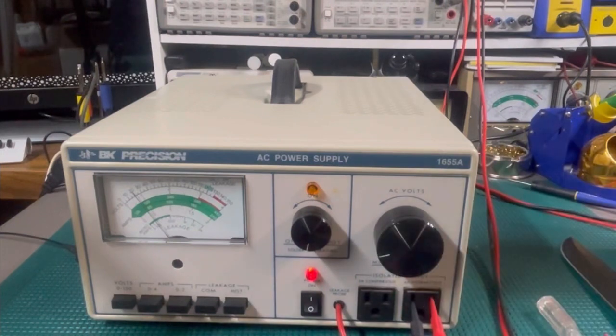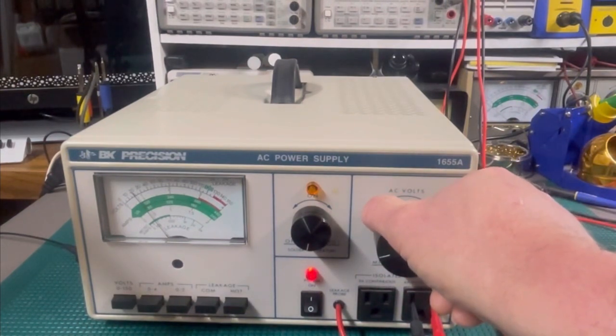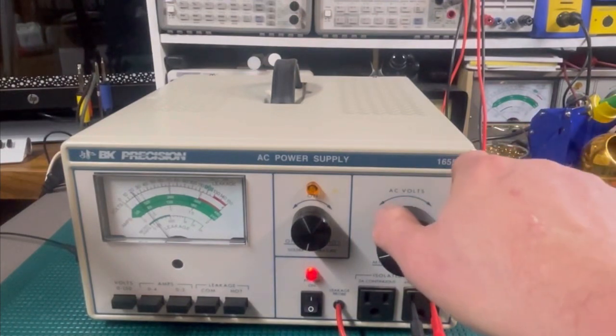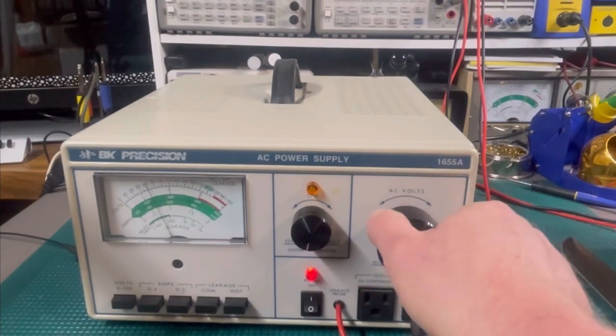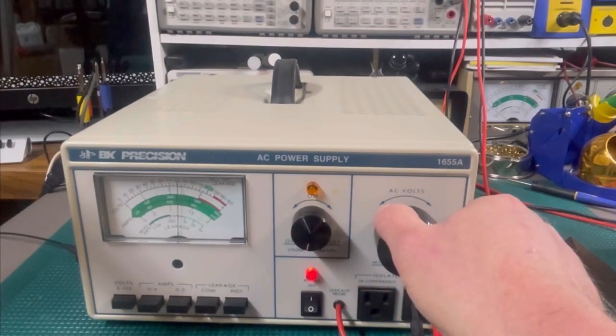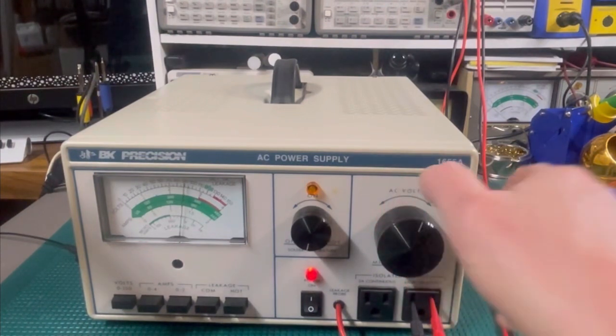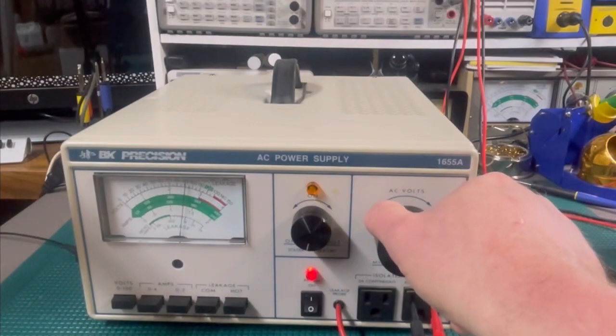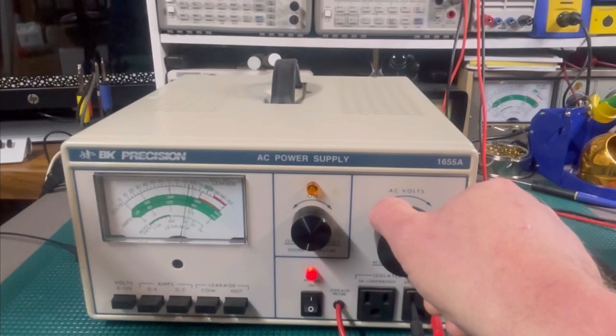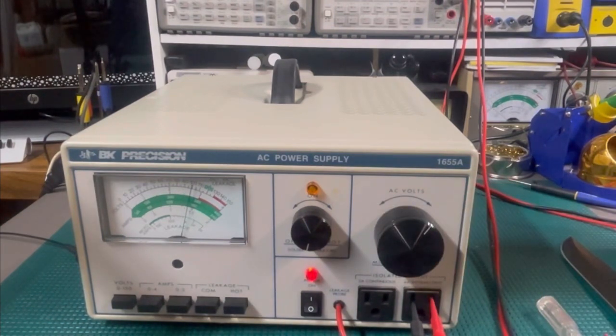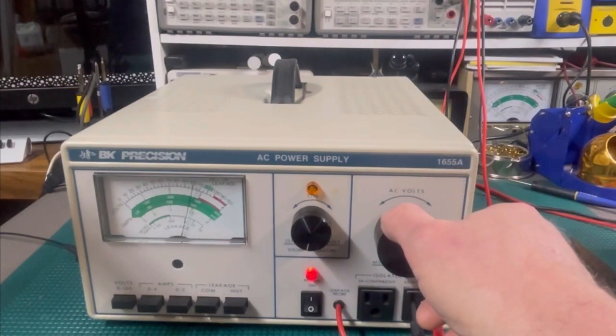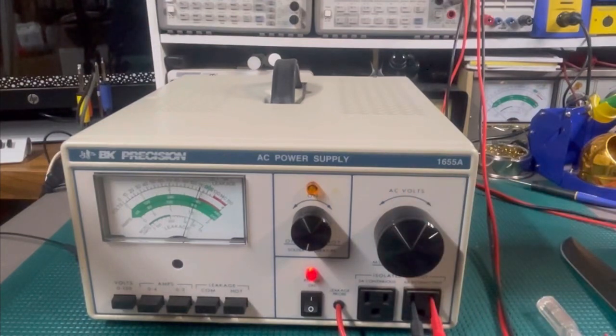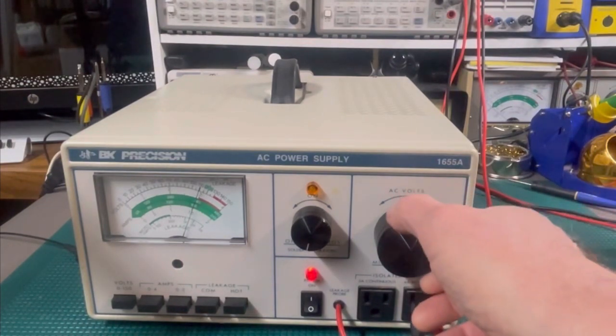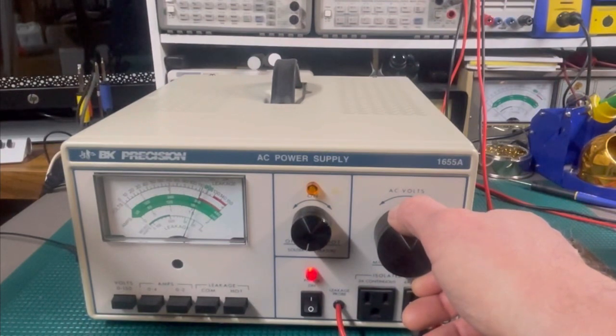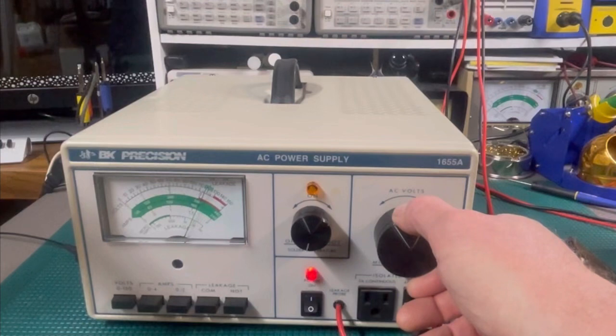Drop it down to 20. Now, let me look at it without parallax. Look at it straight on. We're right at 20. 22. So that's not too bad. Let's see where we start to lose that accuracy. Go up to 90. 87. You know, ballpark-ish. 100. 95. Getting further off. 110. 105. Now it's definitely linearly, or not linearly, it's getting off by a percentage though. So I guess that would be linearly.